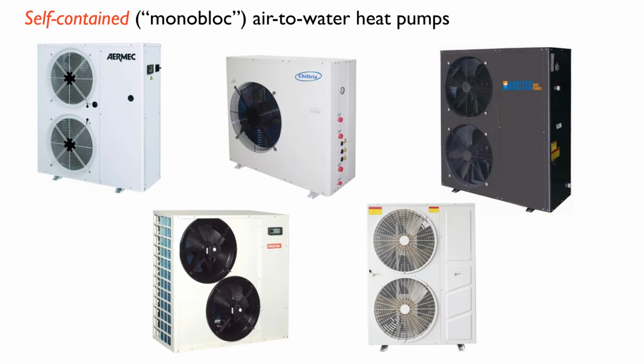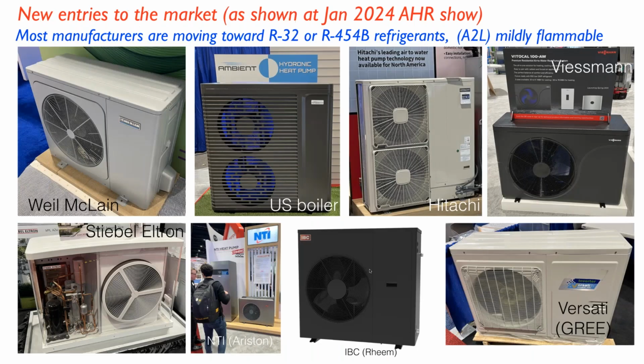Now we're going to look briefly again at air to water heat pumps. There's a lot of products on the market right now. Many of these products are known as monoblock air to water heat pumps, and what that means is that they come factory sealed with factory sealed refrigeration systems. There's no need to connect refrigerant line sets to these. The refrigerant is already in the machine. You're basically bringing out two pipes, running a mixture typically of water and antifreeze, and then bringing out the electrical harness to operate it. So these are relatively simple to install. Pretty much anybody that can do a hydronic system could set one of these units and pipe it, and the electrical is pretty straightforward.